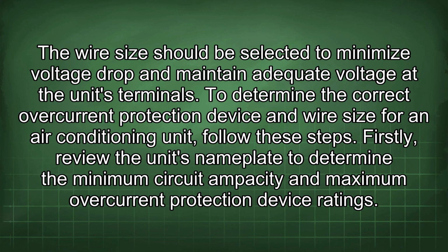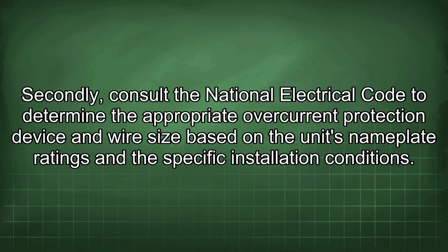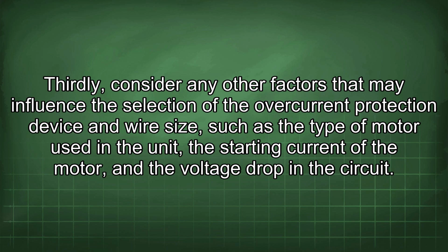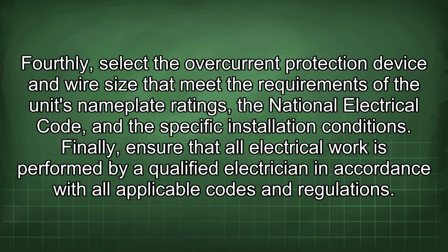To determine the correct overcurrent protection device and wire size for an air conditioning unit, follow these steps. Firstly, review the unit's nameplate to determine the minimum circuit ampacity and maximum overcurrent protection device ratings. Secondly, consult the National Electrical Code to determine the appropriate overcurrent protection device and wire size based on the unit's nameplate ratings and the specific installation conditions. Thirdly, consider any other factors that may influence the selection of the overcurrent protection device and wire size, such as the type of motor used in the unit, the starting current of the motor, and the voltage drop in the circuit. Fourthly, select the overcurrent protection device and wire size that meet the requirements of the unit's nameplate ratings, the National Electrical Code, and the specific installation conditions. Finally, ensure that all electrical work is performed by a qualified electrician in accordance with all applicable codes and regulations.